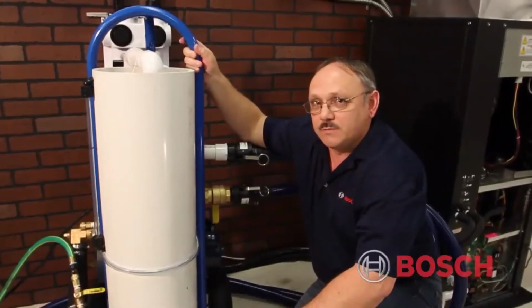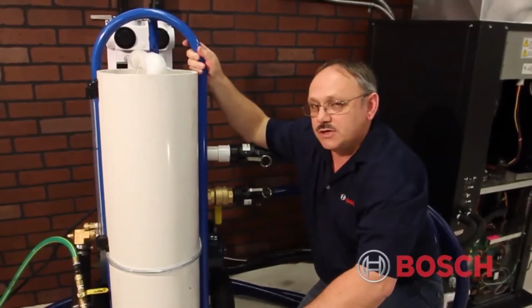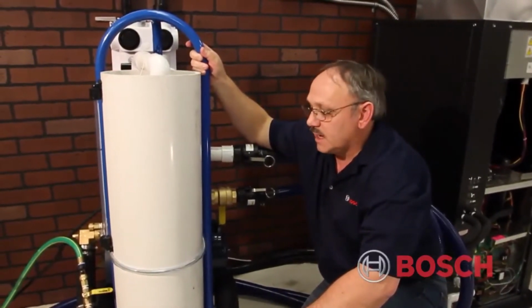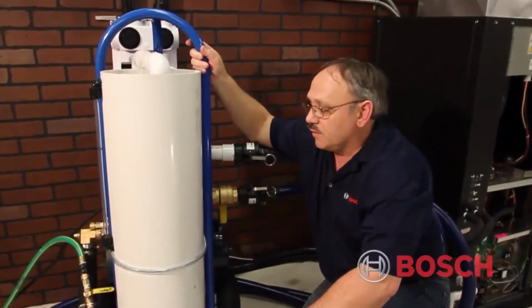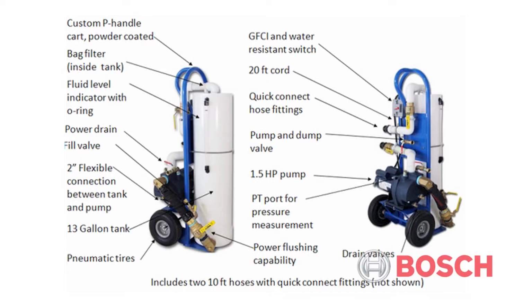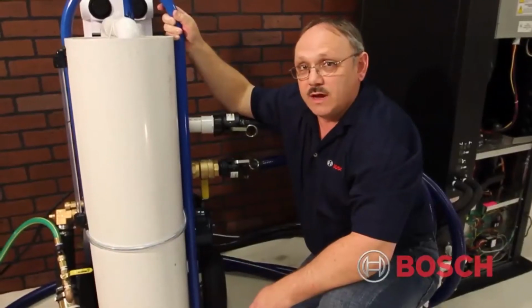The next part of our installation process is the flushing and purging of our heat exchanger and also the system side of our water piping. This is the new GeoFlow flush cart. It is available now through the Bosch accessory catalog. It incorporates a 1.5 horsepower pump, a built-in on-off switch with a ground fault interrupter on it, a 20-foot cord. It is 120 volt. It also has a reservoir tank on it and a series of valves that allows us to fill this reservoir, pump water through our loop system, and flush all the debris out and purge all the air out of the system.